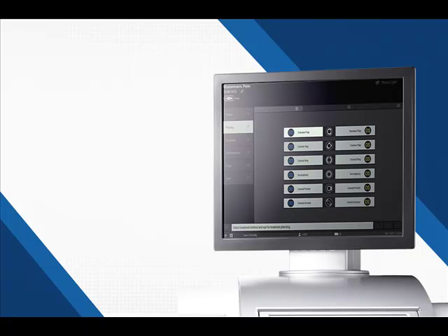There are 2 packets there. Even within the green, they are differently colored. Is there any reason for that? Yes. So the purple color, which is the next slide, the purple color is the standard LensX soft fit patient interface. This is what is inside the box of 10. The catalog number is slightly different, but if you see purple, you know it's a standard LensX patient interface, which is identical to the green one.